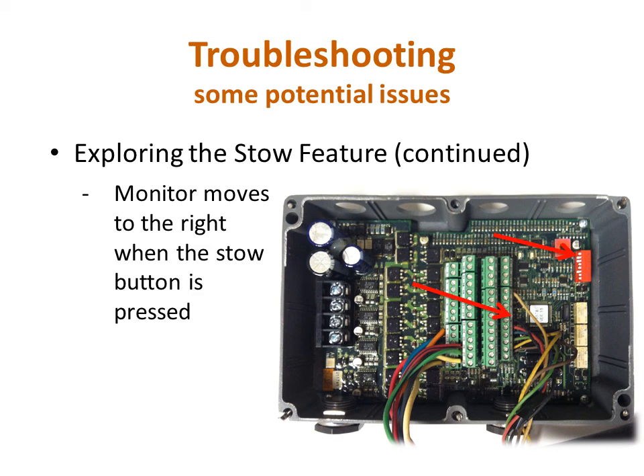to the right. On the other hand, if you momentarily press the stow switch and the monitor rotates all the way to the hard stop, then the sensor has not picked up the magnet, and the sensor and wiring harness will need to be checked for damage. The sensor closes the circuit when it is over the magnet, so the continuity function on your multimeter can be used on the pins of the sensor plug to check that the sensor is functioning properly. The wiring harness needs to be checked as well.